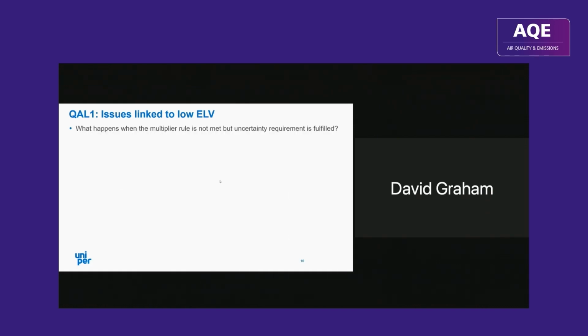So, issues linked to low ELVs. What happens when the multiplier rule is not met, which is a requirement of the standard, but the uncertainty is still okay on the certificate? Sometimes there's a bit of a disconnect between the certification range and the absolute uncertainty. Well, it seems obvious that you would allow the AMS to be used if it has a good enough uncertainty, but that isn't what the standard says.